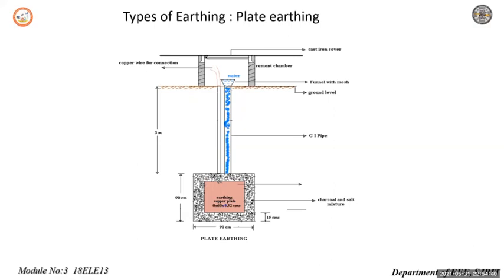The earth lead used must be GI wire or GI strip of sufficient cross-sectional area to carry the fault current safely. We have to carry the fault current safely. The earth wire is drawn through a GI pipe of 19 mm diameter at about 60 centimeter below the ground. The GI pipe is fitted with a funnel on the top. In order to have effective earthing, salt water is poured periodically through the funnel.